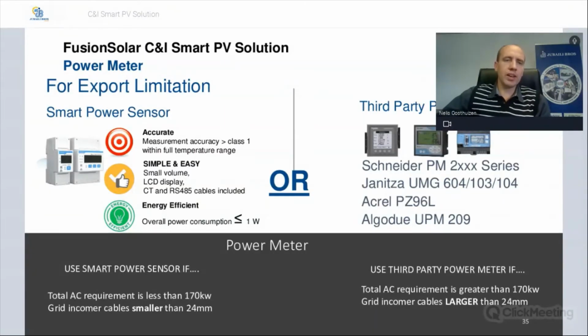Then for export limitation, power meters. As I've mentioned, Huawei has got its own smart power sensors. It's very accurate with a measurement accuracy of class 1. Simple and easy. It's a small volume LCD display, CT and RS-485 cables are included. And then the energy consumption of these power sensors is less than 1 watt.